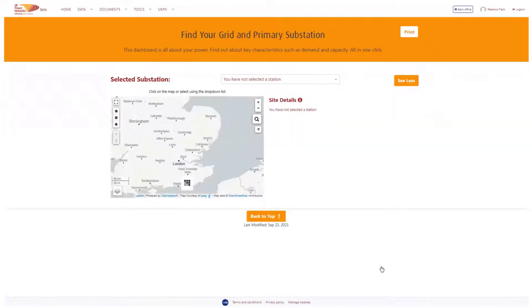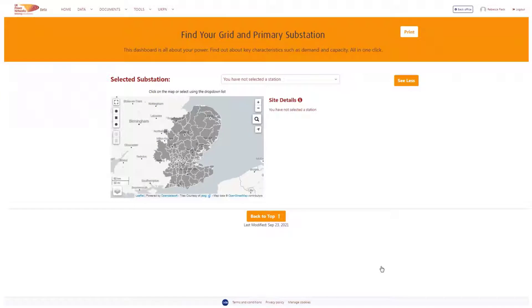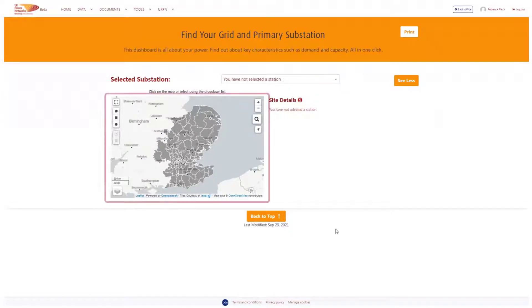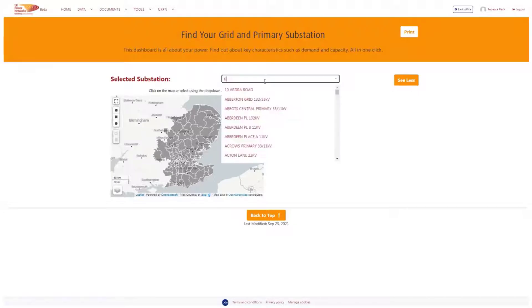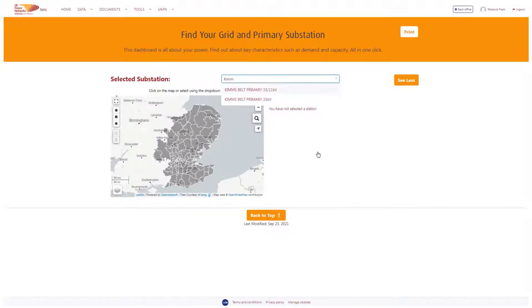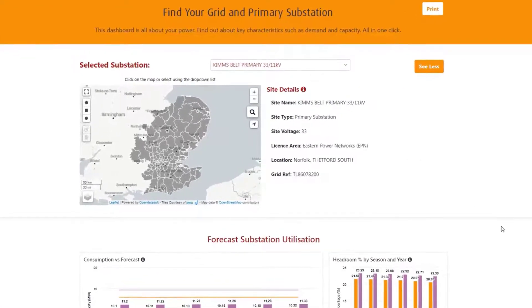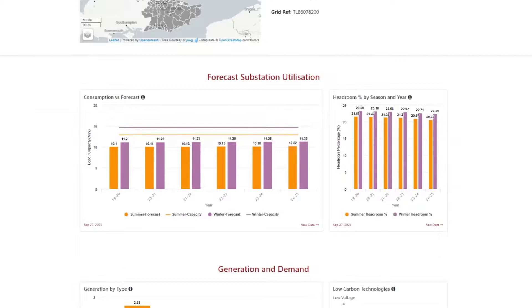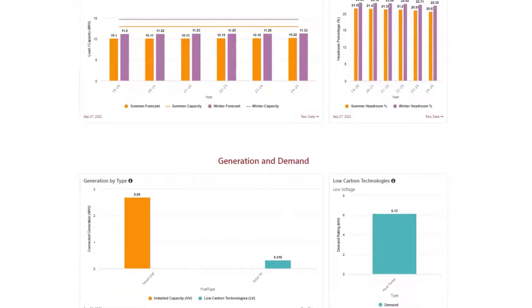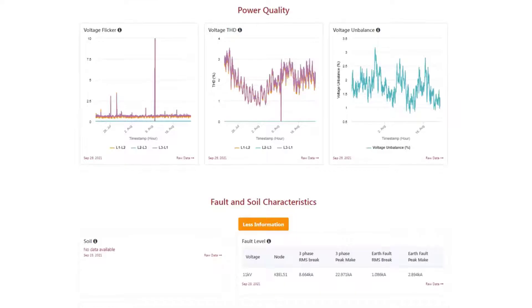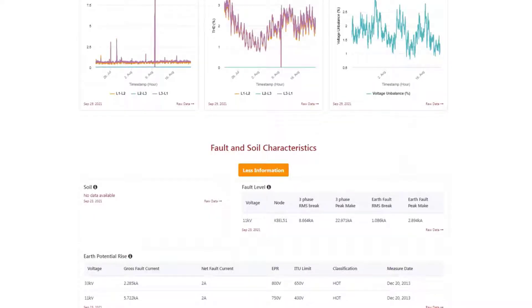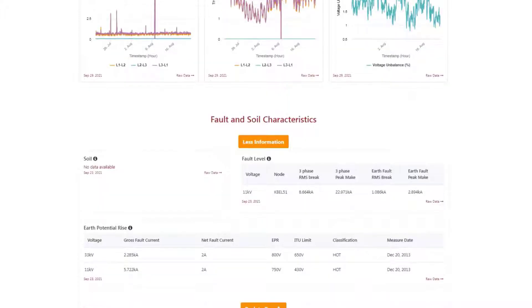This pulls all the relevant network data together for one specific grid or primary site. Using the map, you can select the local authority area that you're interested in and click on the substation of interest, or use the dropdown list if you know the name of the site. The dashboard shows key details about the substation, including capacity forecast and headroom, existing generation and demand where available, and greater depth of detail such as future energy scenarios, power quality, and fault earthing and soil characteristics for enhanced insights to assist with potential developments and new connections in the area.